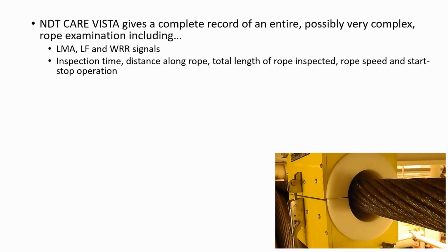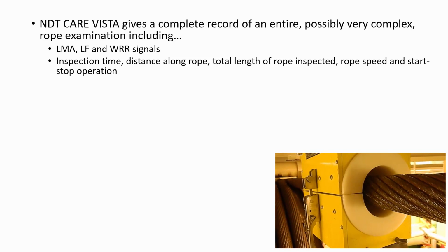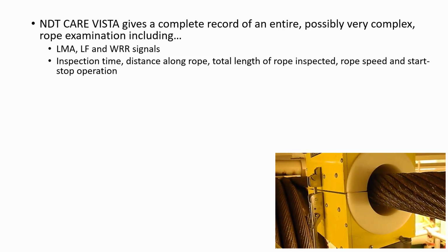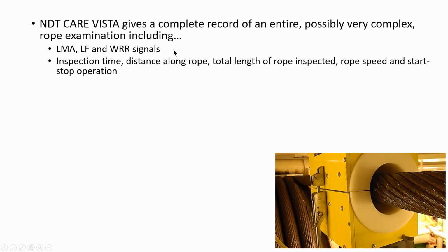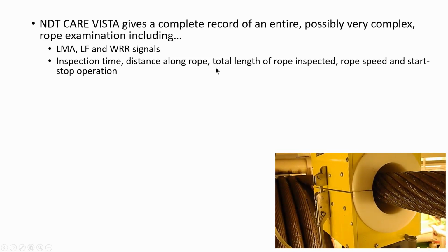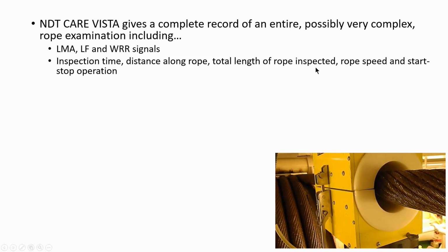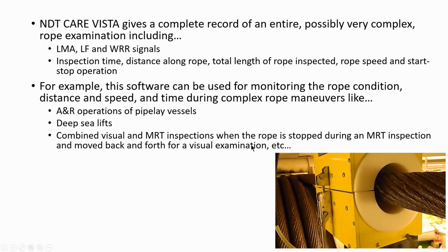The NDT Care Vista gives a complete record of an entire, possibly very complex rope examination, including LMA, LF, and WRR signals, as well as inspection time, distance along rope, total length of rope inspected, rope speed, and start-stop operation.